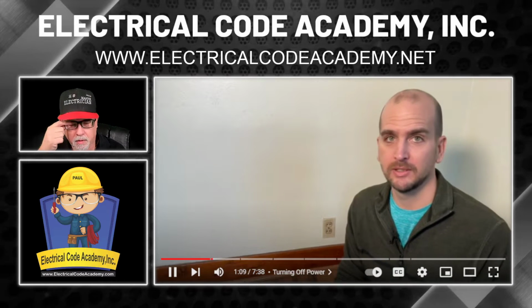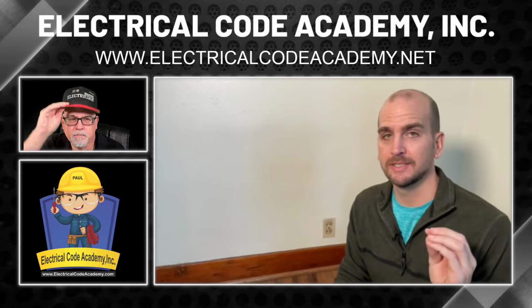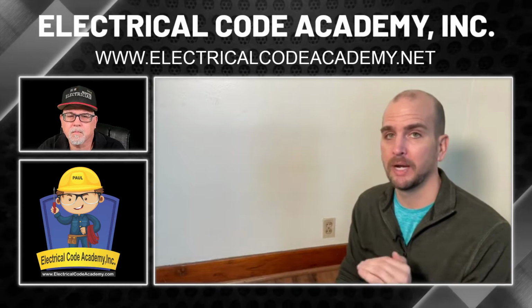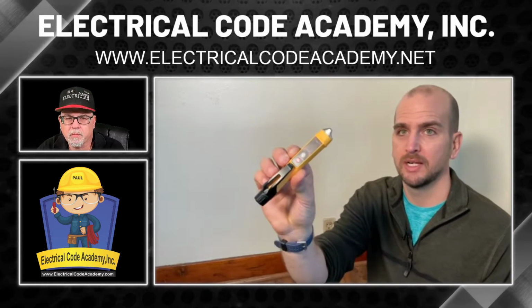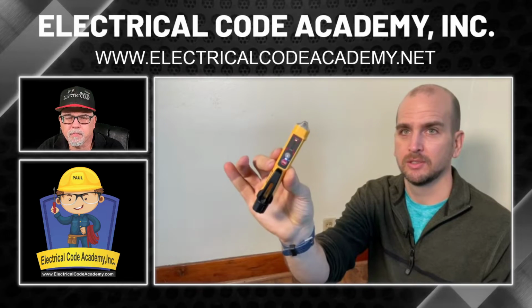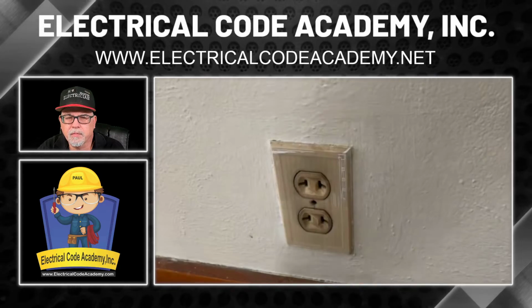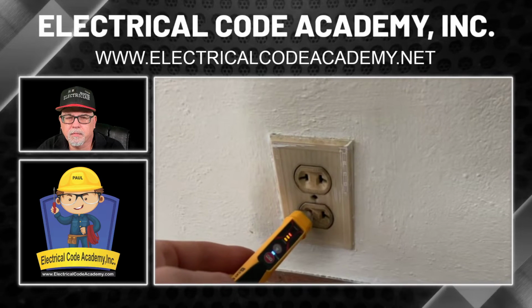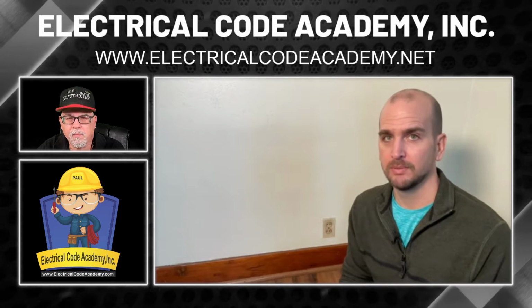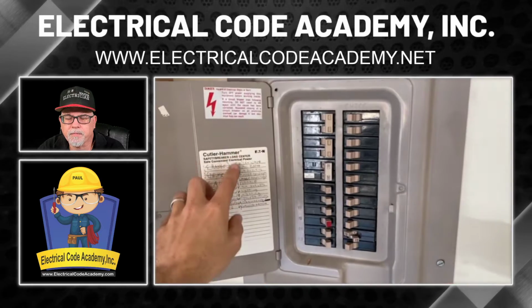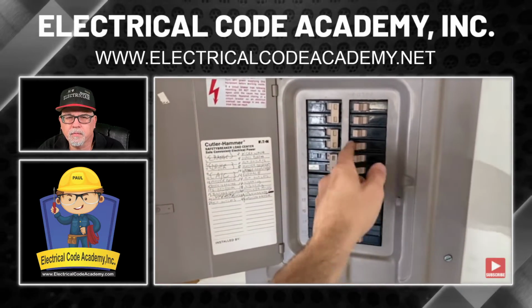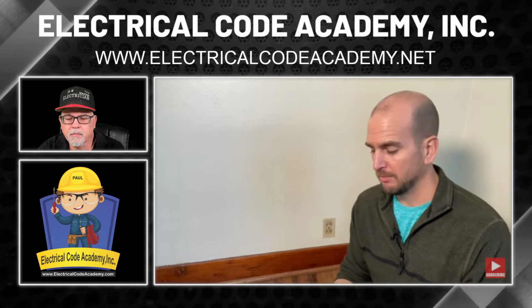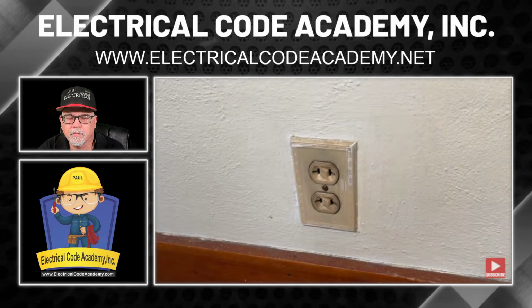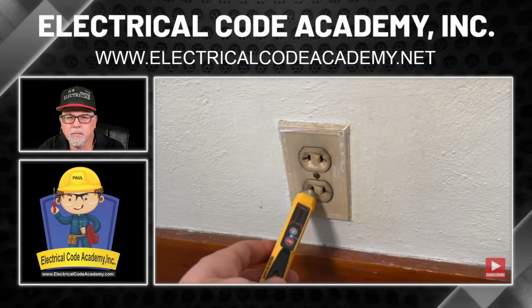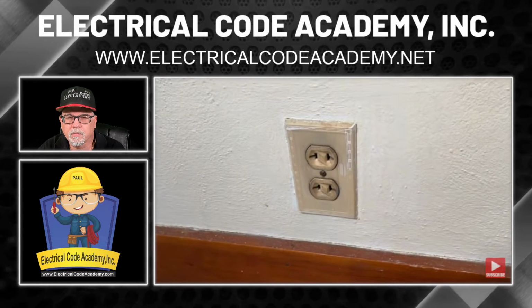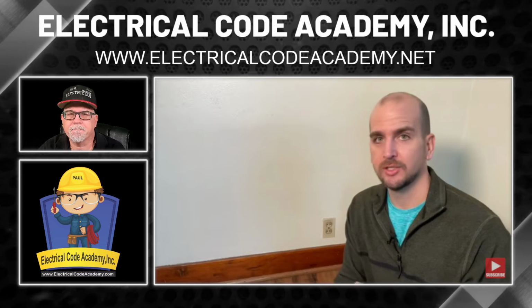So the way we start off any of these electrical projects is to make sure we can safely work on this receptacle and there's no power going to that. To do that, I'm going to use a non-contact voltage tester. I'm going to turn it on and I'm going to test this receptacle to know that my voltage tester is working and power is still going to this receptacle. Once I've confirmed that, then I'll go hit my breaker to turn off power to this circuit. Then I'll come back in. And with the same voltage tester, I will test it again, confirming there is no power going to this receptacle. And once you do that, now we're ready to install the GFCI outlet.